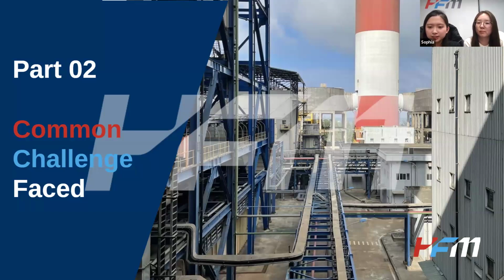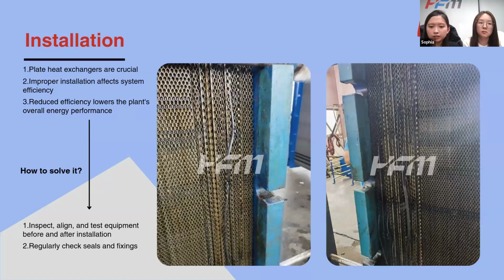So absolutely, she just mentioned a typical problem that often happens. But there are also many other problems that happen with plate heat exchangers. I will go through them with you one by one. The first problem is the installation problem. Improper installation may lead to unstable or inefficient operation of the equipment, and this may affect the performance of the entire heat exchanger. How can we solve it? We must ensure that the equipment is inspected, aligned, and tested before and after installation, and that the condition of seals and fixings is regularly checked to prevent improper installation and long-term operational problems.